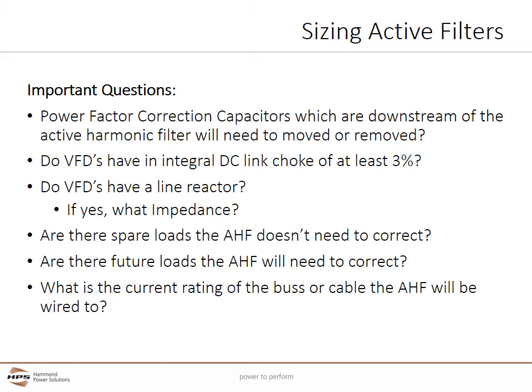There are some important questions which need to be answered when sizing active harmonic filters. If there are power factor correction capacitors downstream of the active harmonic filter — that is, between the active harmonic filter and the VFDs — they will need to be removed. Do VFDs have an integral DC link choke of at least 3%? Many VFDs below 10 horsepower do not have DC link chokes, so they will probably need line reactors. Do the VFDs have a line reactor, and if yes, what is the impedance? Are there spare loads that the active filter doesn't need to correct for, like across-the-line start motors or resistive heaters? Are there future loads the active harmonic filter will need to correct for? And what is the current rating of the bus or cable the active harmonic filter will be wired to, so the current sensors can be accurately sized?